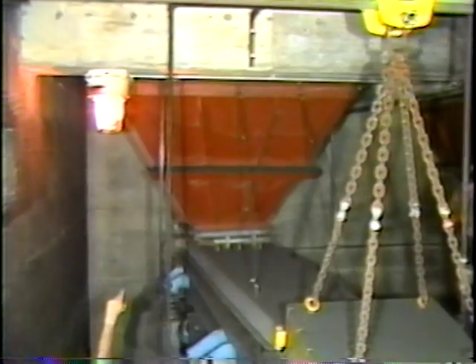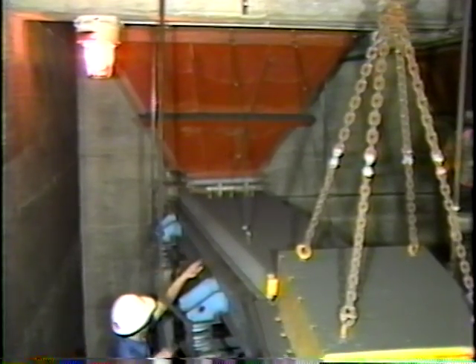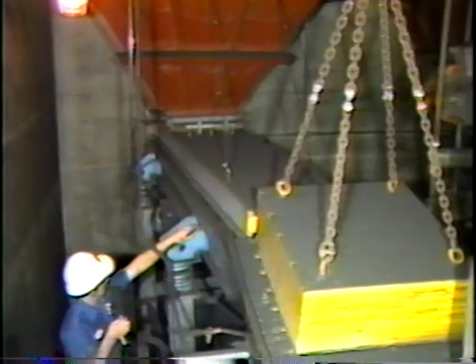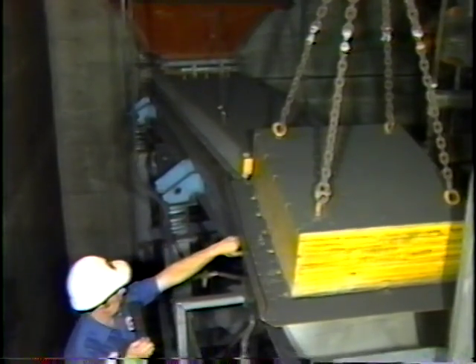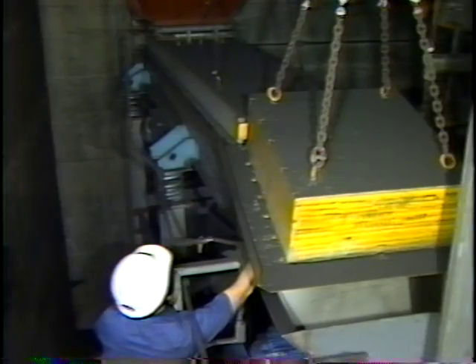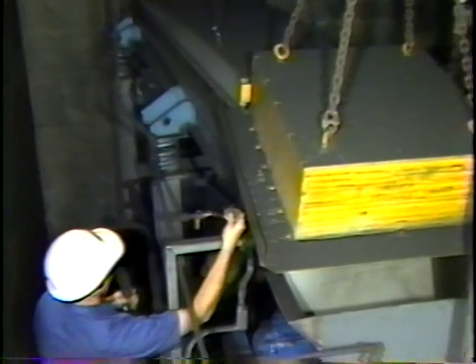The truck receiving hopper, located directly below the Grizzly, is designed to receive 40 tons of coal in 2 pyramidal hoppers. At the base of each pyramidal hopper is a vibratory pan feeder, which conveys the coal at 50 tons per hour to a 50 ton per hour single roll Williams crusher.